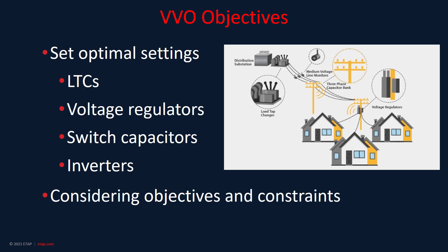VVO-C finds and sets the optimum settings of voltage and VAR control devices, optimizing Volt-VAR in the distribution network by adjusting the load tap changer, voltage regulator, and capacitor. It brings up voltage levels by changing tap positions on transformers and reduces VAR flow to minimize overall voltage drop and reduce power loss.